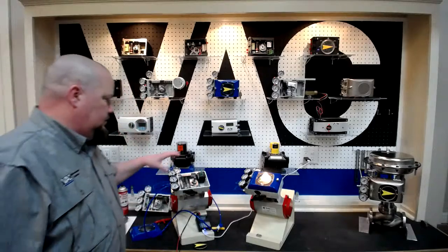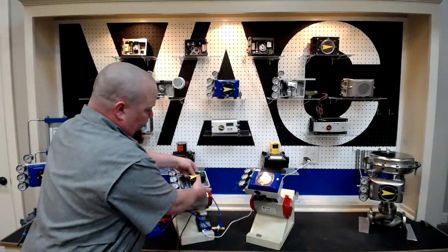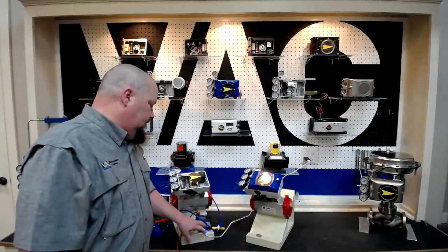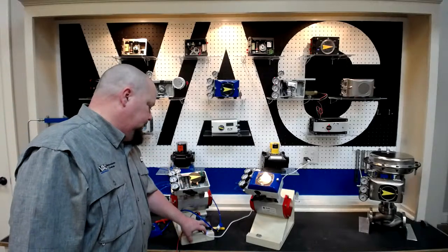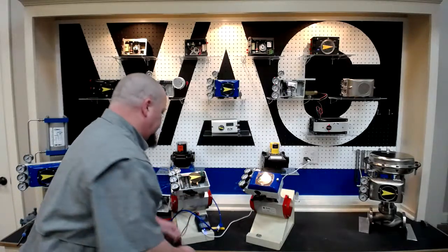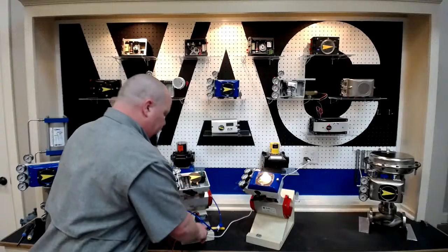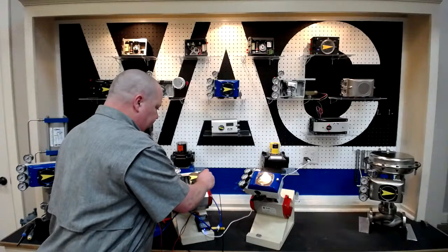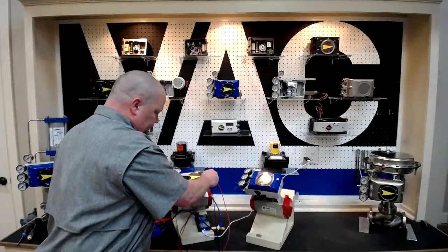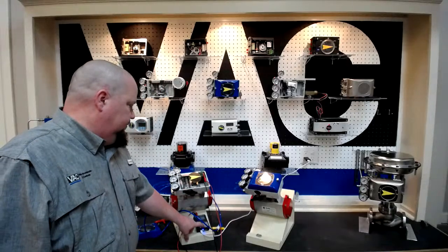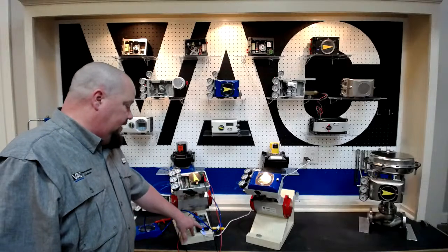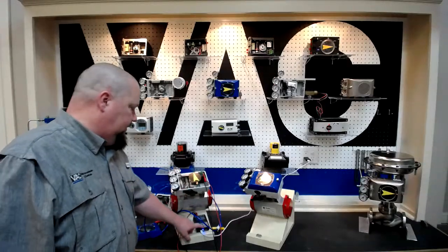So currently, we've got it at 4 milliamps. I'm going to put the indicator on so you can see it a little better. Now, as I increase signal, what is going to happen is we're going to see the positioner move, but it's not going to move quite properly. So as we increase signal, we see that it almost went all the way open on an 8 milliamp signal change. So this is 20 milliamps.